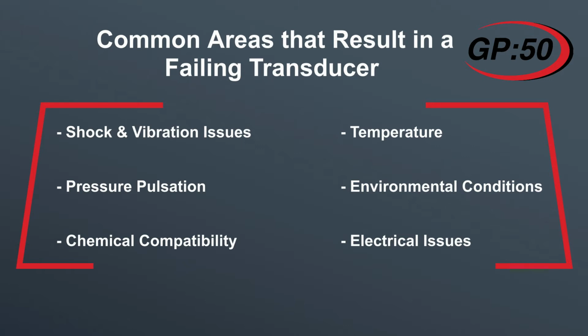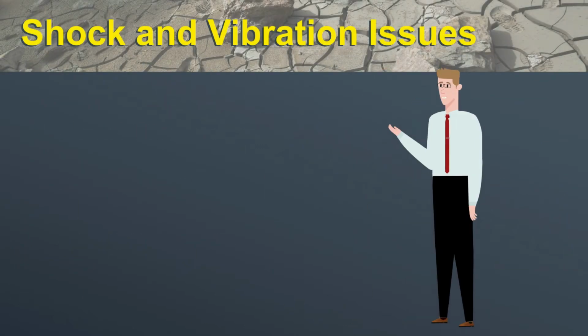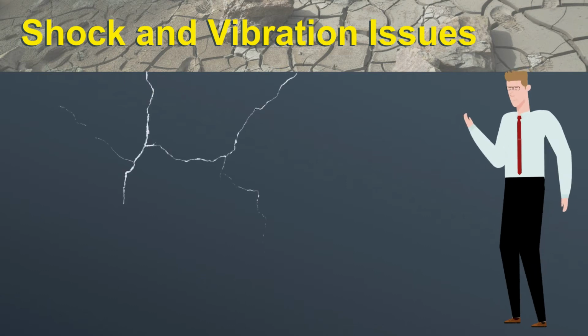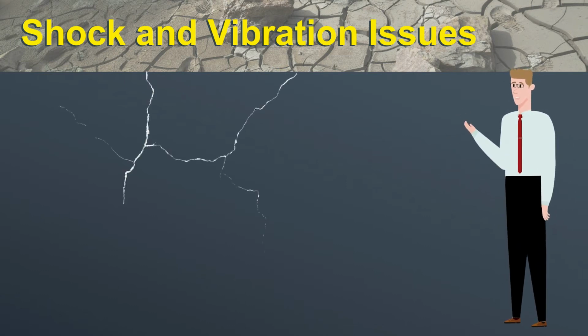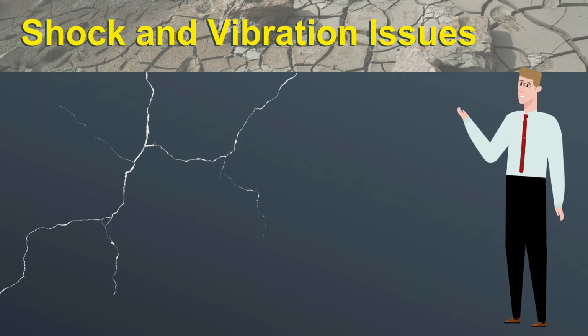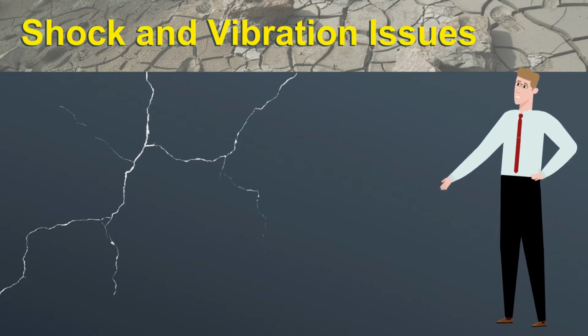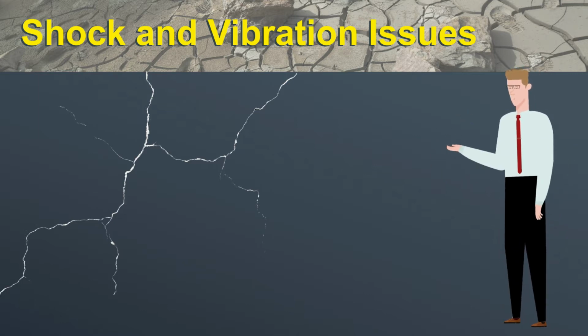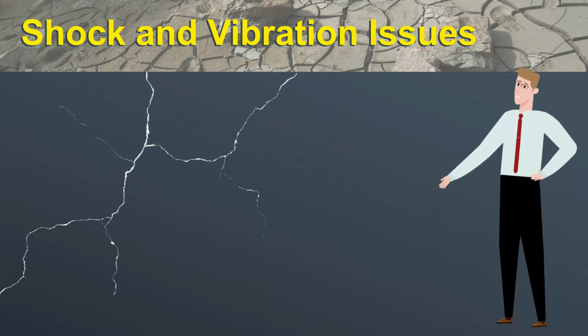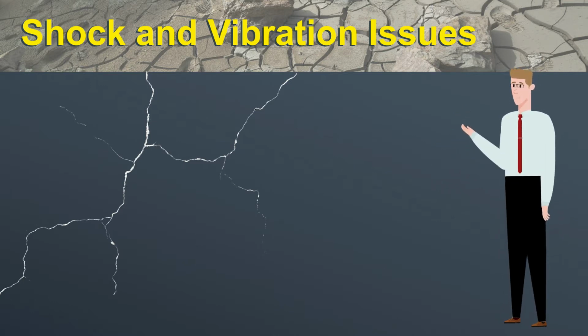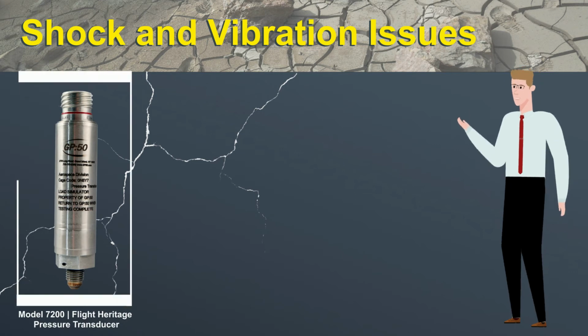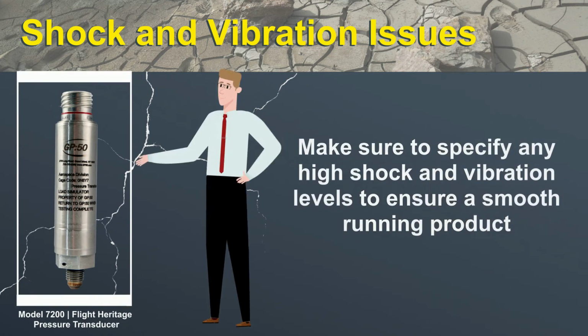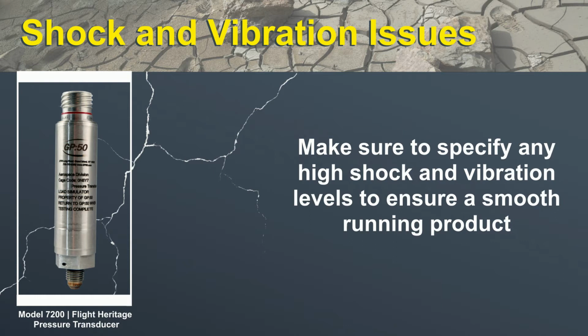pressure transducer. High shock and vibration levels can have a severe effect on the longevity of a pressure transducer. While GP50 designs robust products, knowing these levels before purchasing a product can be the difference between a unit failing after a month to a reliable unit running smoothly for years. Providing this information to GP50 when specifying a unit will help us provide the best option for the application.